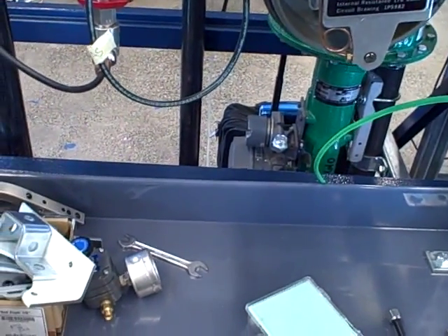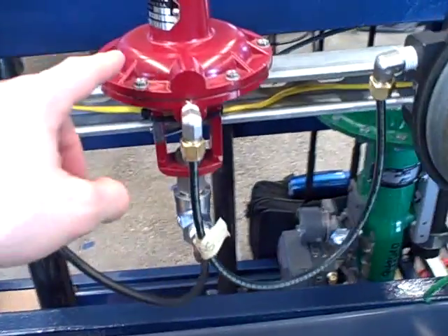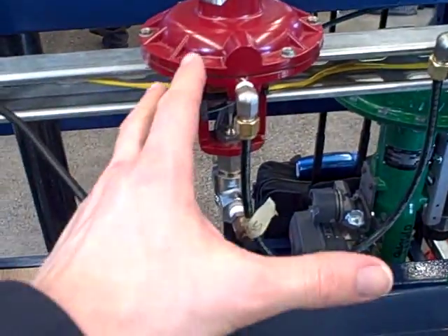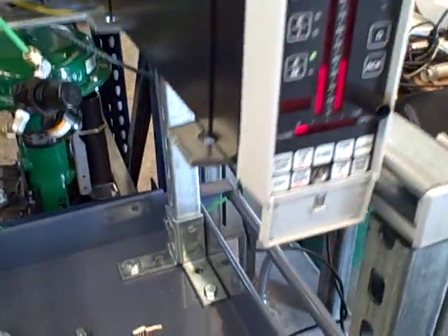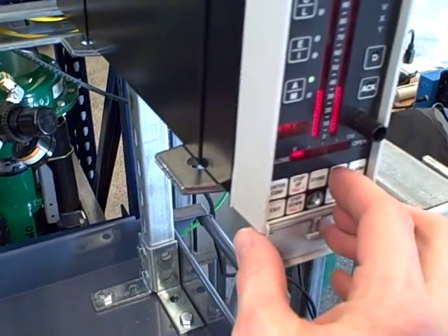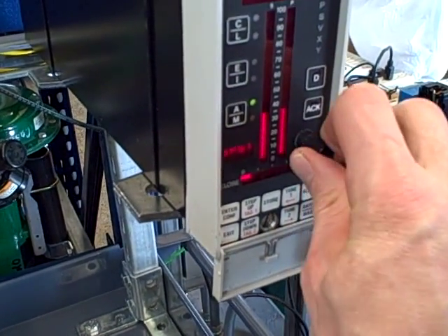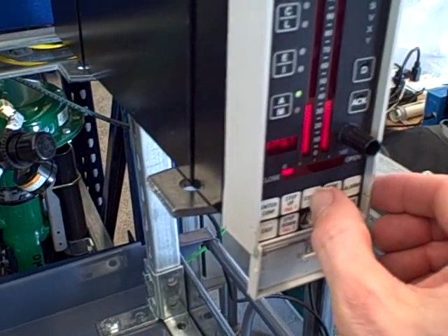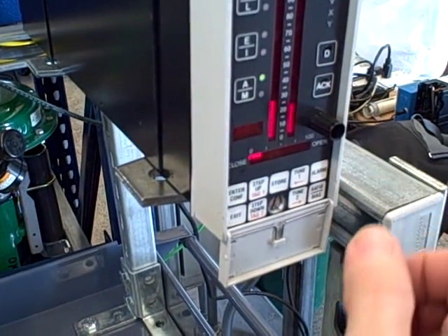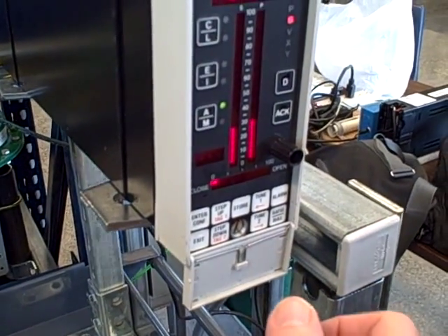This can be greatly helped if we were to put in a valve with an equal percentage trim, which will tend to negate that process distortion. Until we get a valve with the right trim, we'll do the best we can with tuning, our best compromise. We can turn down the gain a little bit, from 1.56 down to, let's say, 1.18. We'll store that. And here, it's not going to oscillate quite as bad at the bottom.